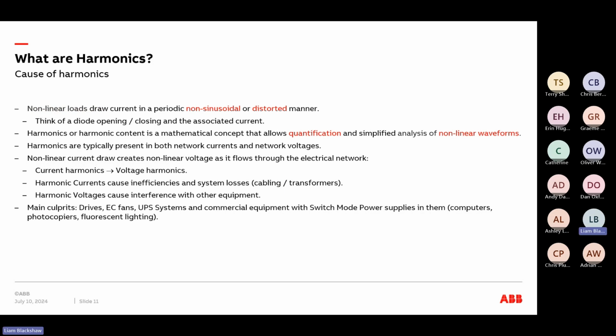So when we look at the cause of harmonics, the cause of it is nonlinear loads that draw a current in a periodic, non-sinusoidal or distorting manner. The best way to think about it is of a diode opening or closing and its associated current, and how we're applying effectively an AC signal to a DC component. And the harmonic content is a mathematical concept that allows the quantification and simplified analysis of nonlinear waveforms. It's present in both network voltages and currents. But as a result, it's the nonlinear current draw that creates that nonlinear voltage as it flows through the electrical network.